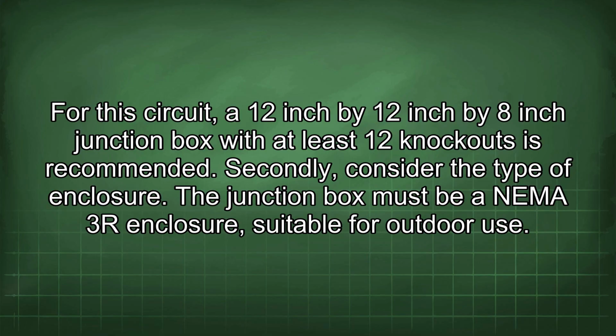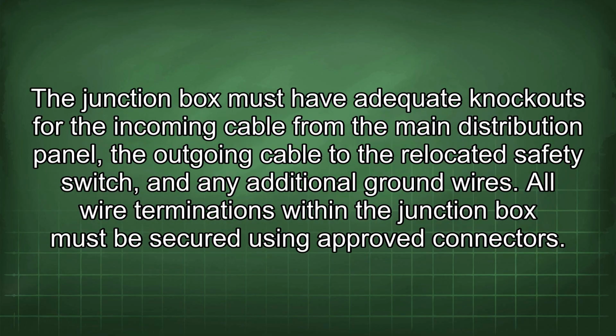Secondly, consider the type of enclosure. The junction box must be a NEMA 3R enclosure suitable for outdoor use. The junction box must have adequate knockouts for the incoming cable from the main distribution panel, the outgoing cable to the relocated safety switch, and any additional ground wires. All wire terminations within the junction box must be secured using approved connectors.